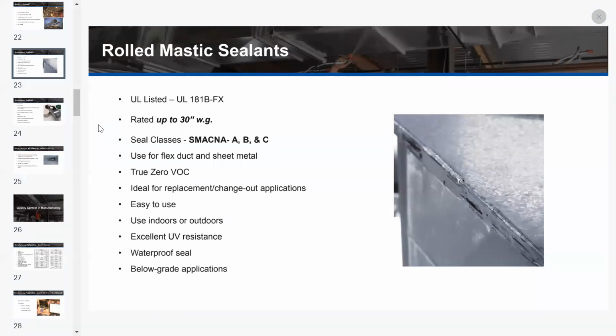It is the only true zero VOC duct sealant that's in the market because it's 100% solids. It's fully cured when you get it, actually when it comes off of the equipment. Ideal for replacement, change out applications. It's very easy to use. You can use it indoors or outdoors. Has excellent UV resistance because it has a foil facer. Typically 2 mils of foil and about 17 mils of butyl. And then we have a thicker version as well that goes actually up to 30 mils.